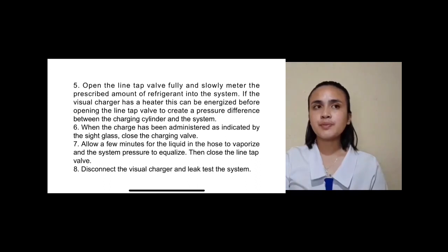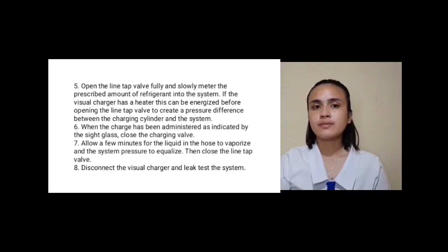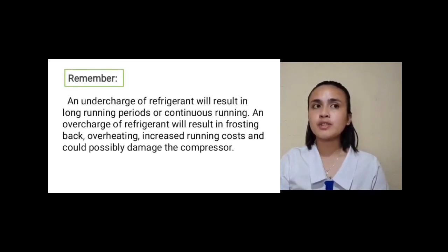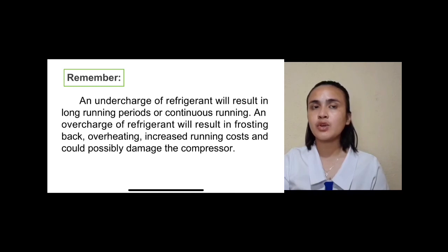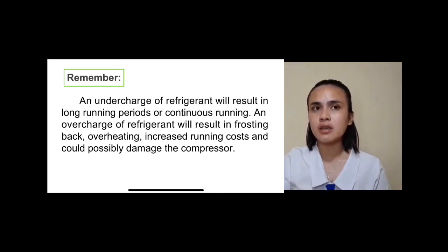So that's the process of charging refrigerant in a domestic refrigerator. And remember, an undercharge of refrigerant will result in long running periods or continuous running. An overcharge of refrigerant will result in frosting back, overheating, increased running costs, and could possibly damage the compressor.